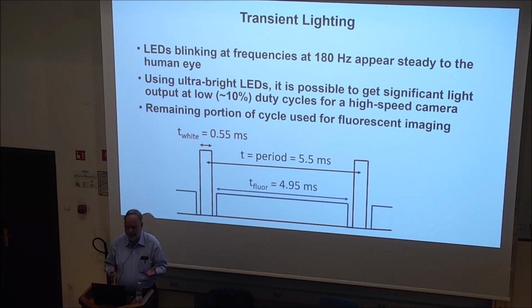So we use 180 hertz cameras to look at both a white light image and a fluorescent image. And of course, the fluorescent camera, we have to have special filters in front of it to get rid of the excitation light as well. So basically then the period is 5.5 milliseconds, with the white light portion being 0.55 milliseconds at 10% duty cycle. And about 90% of the time you can get the fluorescent signal free of any white light, right? And so we said, well, this can be implemented in surgery as well.